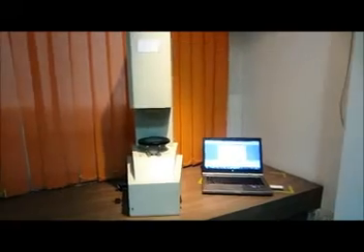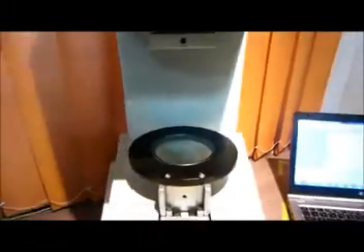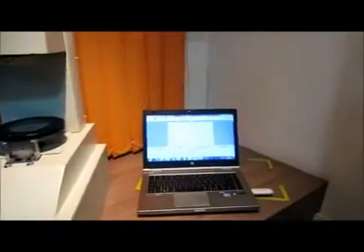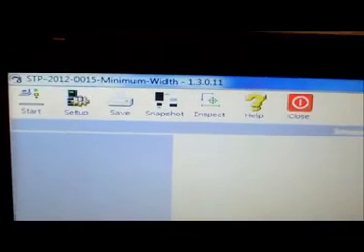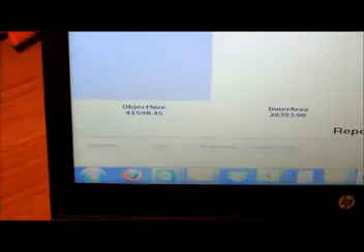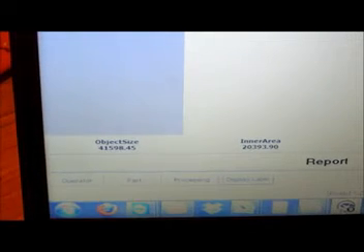In this case, you have to keep a sample on the glass plate here. Like we have kept a 6-core sample on the glass plate, and then the system is connected to a very interactive graphical user-based software for measurement, which has all the icons on the top. Like you can see that, you can see an icon for start, setup, save, snapshot, inspect. Then at the bottom we have certain icons like operator, part, processing and display labels, where you can feed in the required details for the measurement. And then we have a big icon for report for reporting and analysis purposes.